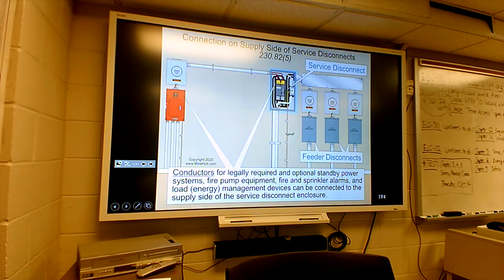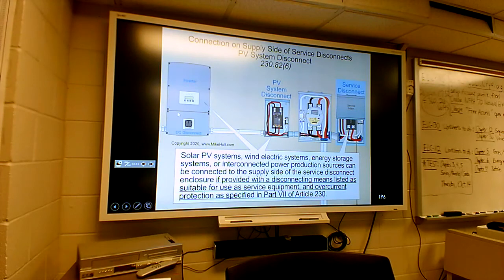So here, when you see something in red, that's typically going to be for sprinkler systems or some type of specialty system like that. They'll be painted red or orange. Conductors for legally required systems, you see where they're tapped in? They're tapped into the top, not the bottom. So where you're coming in from the power company up here to the top of that main disconnect, that emergency system right there is tapped in up top, so that if your service disconnect gets shut off, it will not affect, say, the sprinkler system or something like it. They're going to get power straight from the power company with no way to interrupt it. The same thing for photovoltaic, for your solar equipment outside the house.